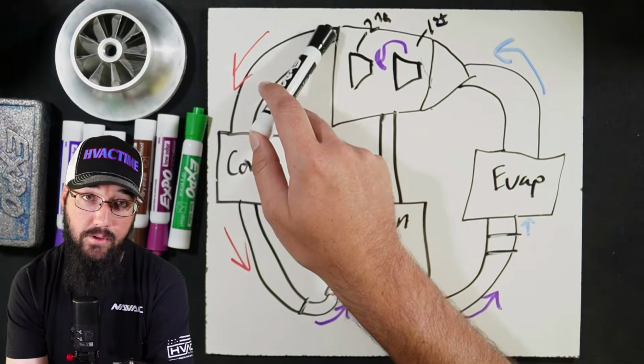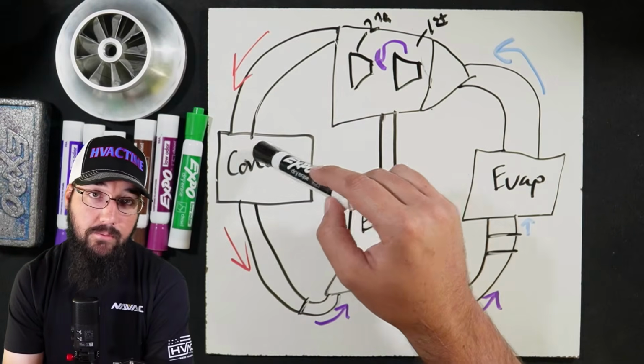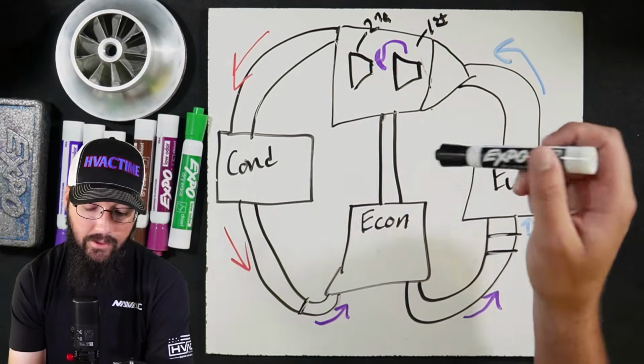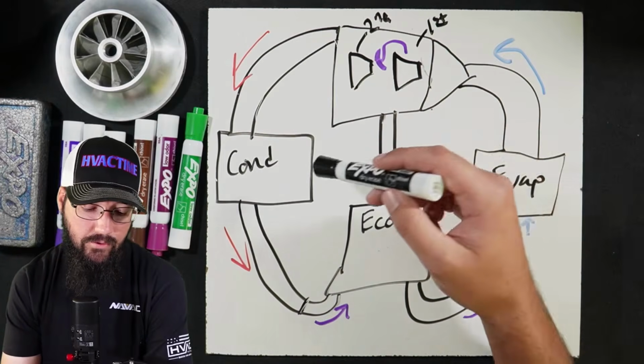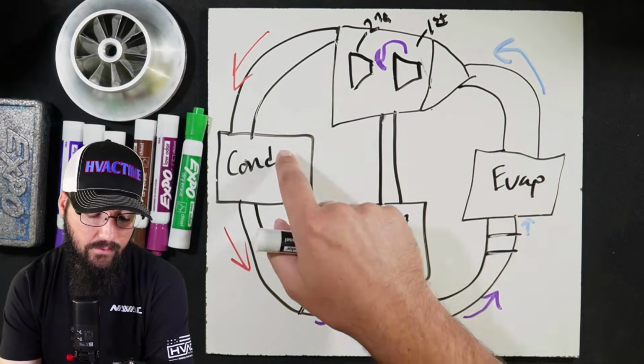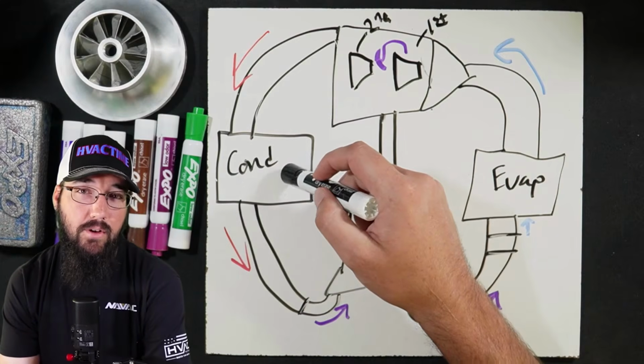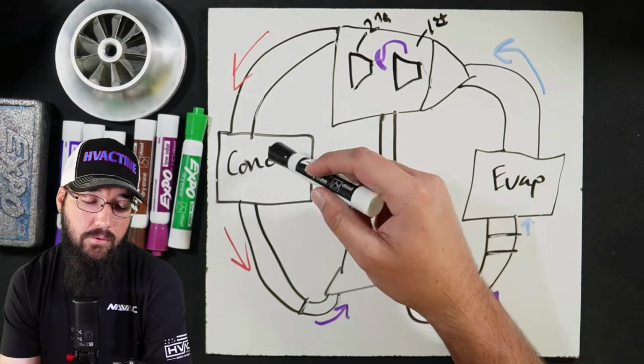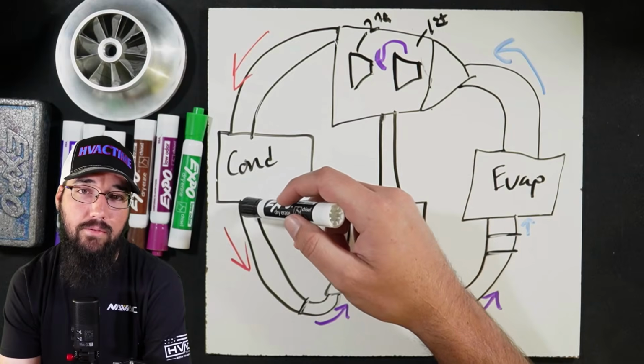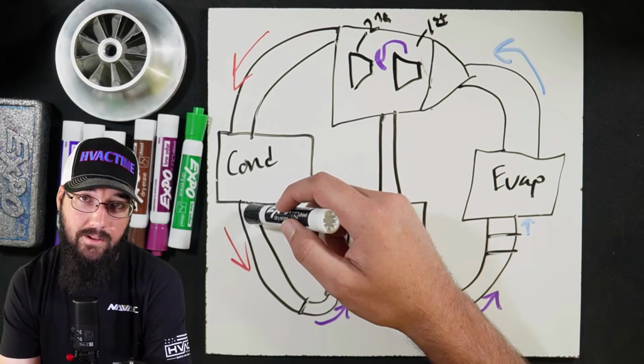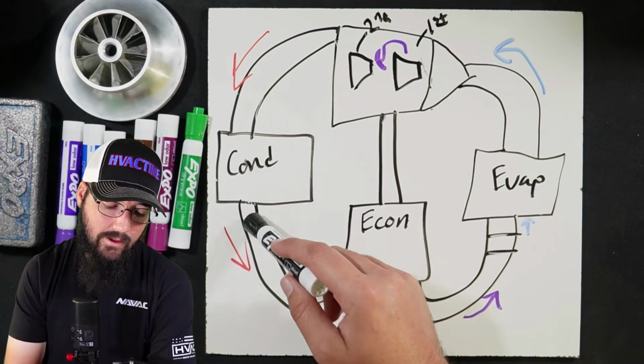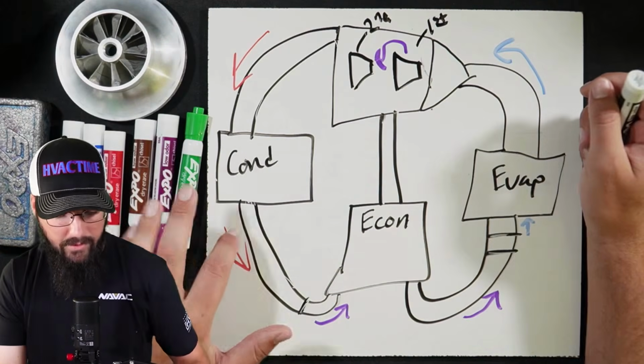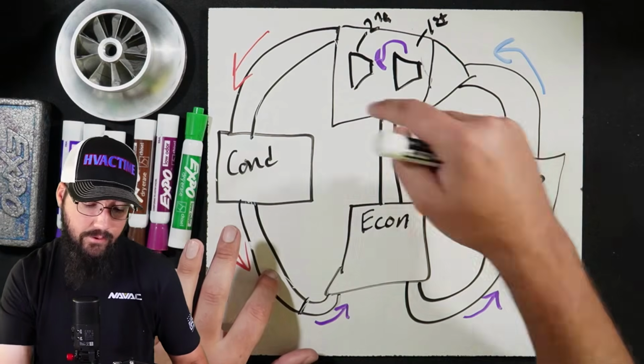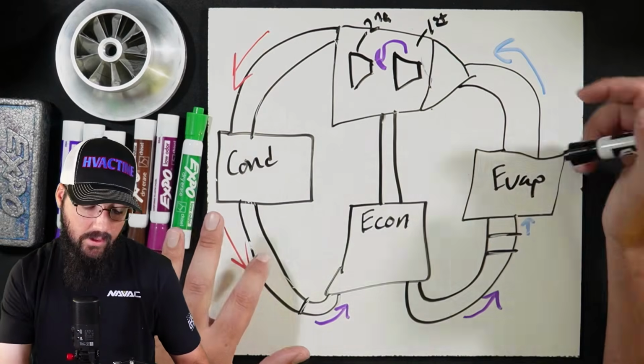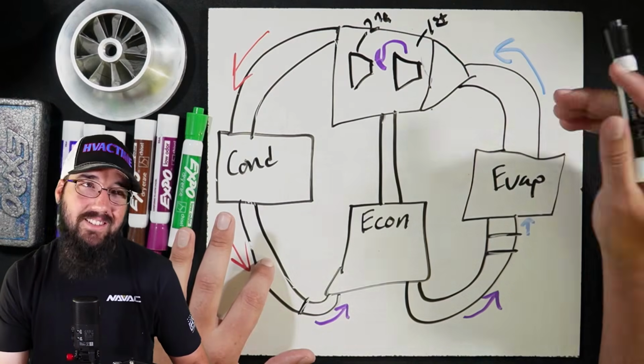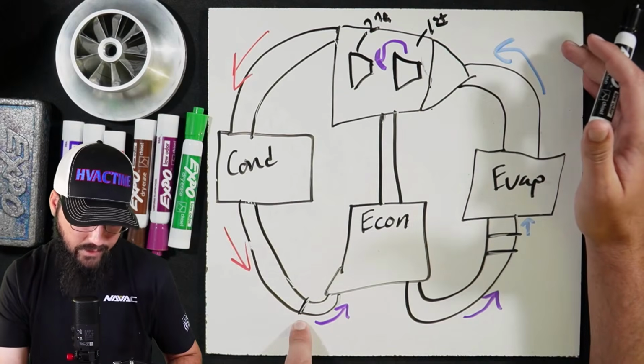So out of here we come high pressure refrigerant. Discharge gas comes into the condenser. The condenser condenses the discharge gas accordingly. These are both water-cooled heat exchangers, condenser and evaporator. These particular condensers generate a very minimal amount of subcooling. Basically, it's just enough subcooling to ensure that we have a full column of liquid coming into our drop leg. The drop leg, or the liquid line, is the line leaving the bottom of the condenser. When we come down out of this line, we're still a high pressure liquid refrigerant. So high pressure superheated discharge gas, high pressure slightly subcooled liquid refrigerant. We come into a flash plate.